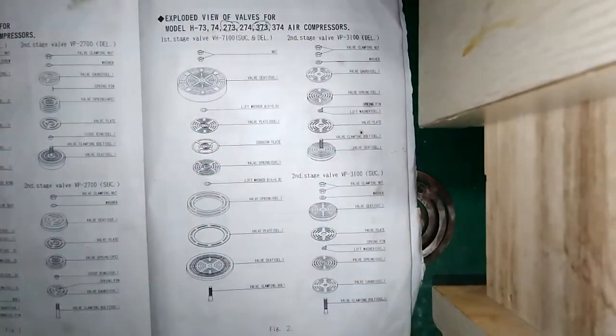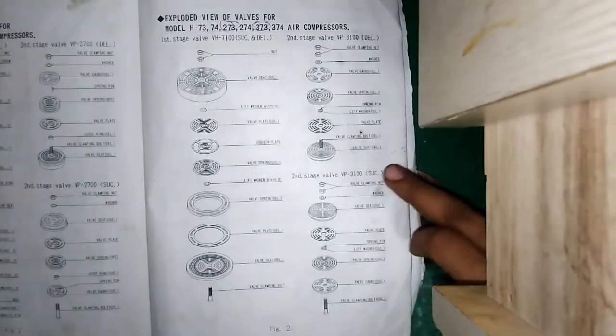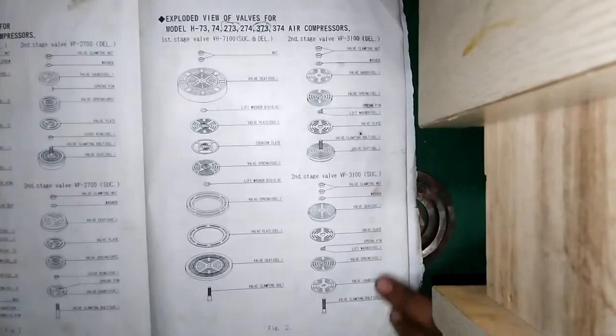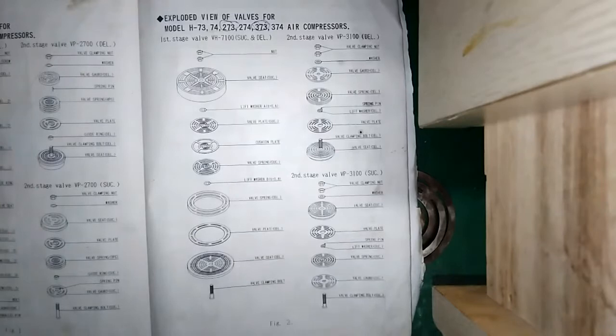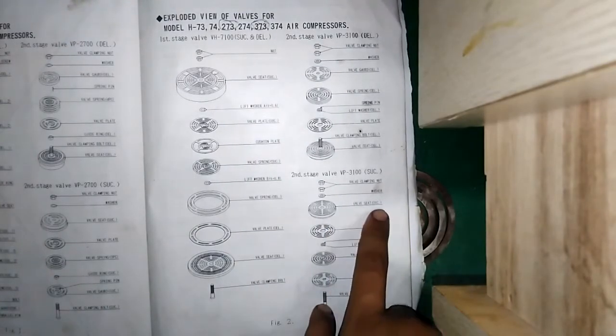The torque by which you have to tighten it is 24.52 Newton meters for the VP-3100S, or 250 kilogram-force centimeter. This page is most important. In this page it is the exploded view of the valve for the model H-273.